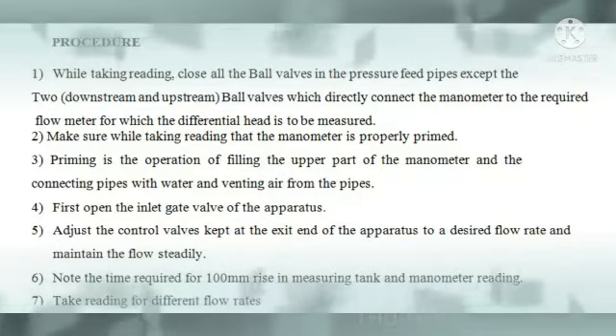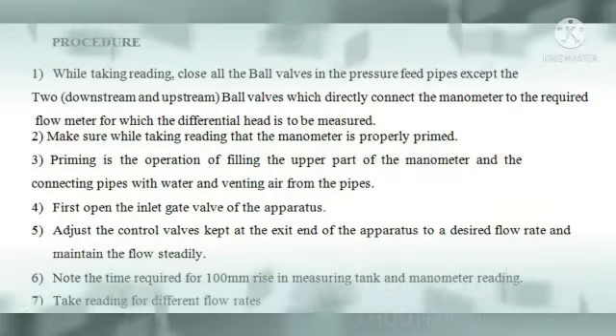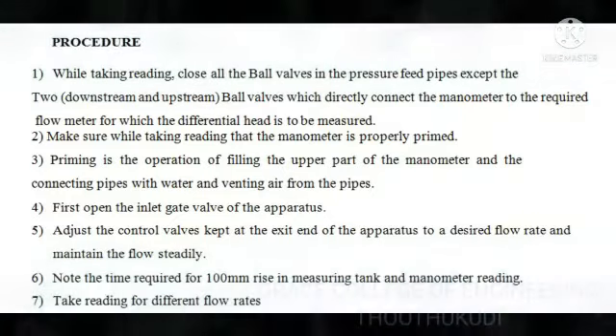Note down the time required for 10 centimeter rise in the measuring tank and take down the manometer reading. We have to continue this for different flow rates.